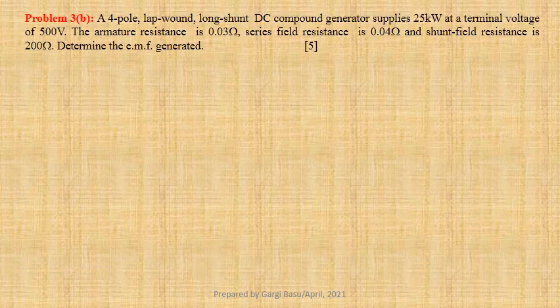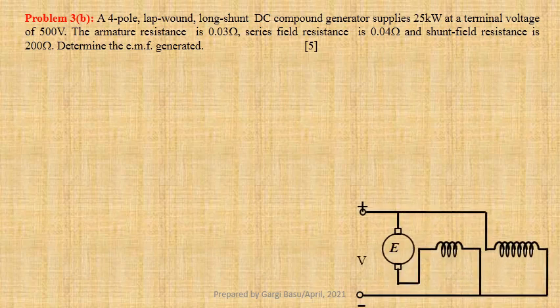Problem number 3b. A 4-pole lap-wound long shunt DC compound generator supplies 25 kilowatt at a terminal voltage of 500 volts. The armature resistance is 0.03 ohm, series field resistance is 0.04 ohm, and shunt field resistance is 200 ohm. We have to calculate the generated EMF.